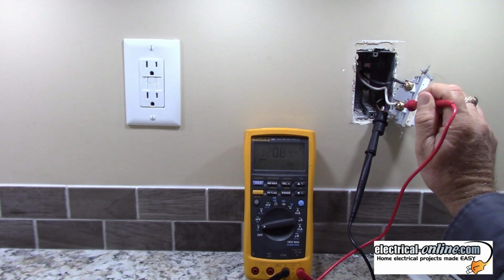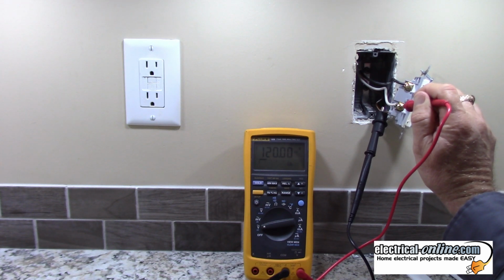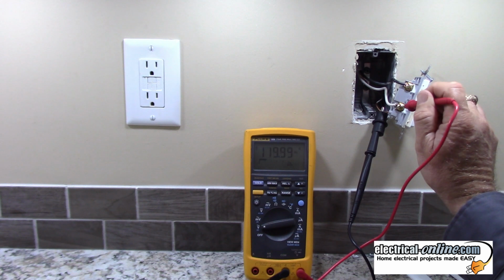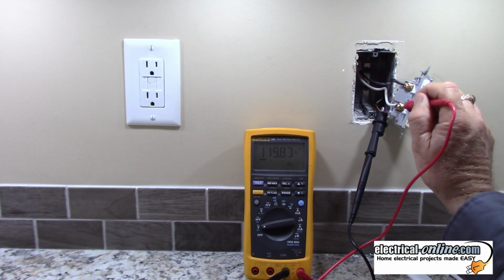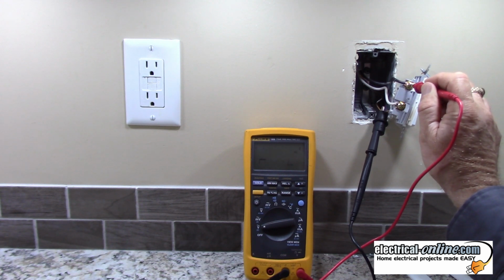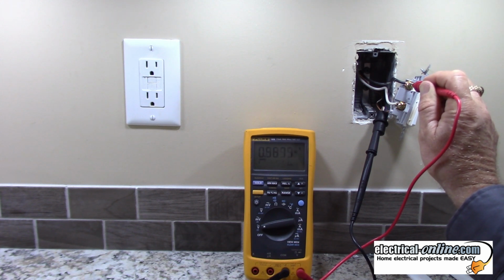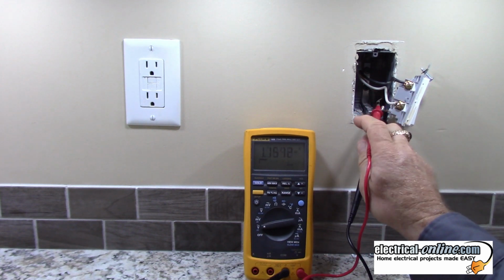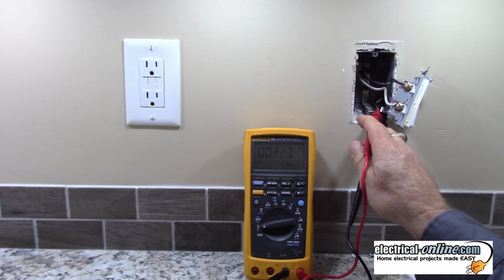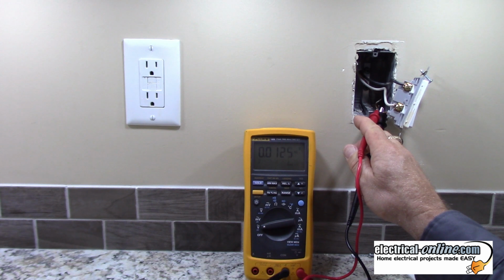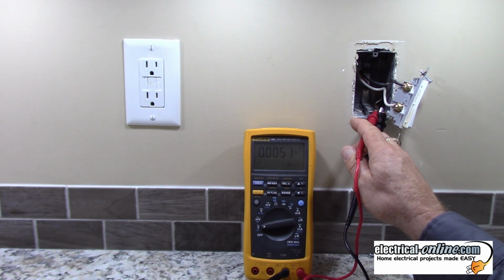And then we should only have power on one terminal, and that's the white, which is being used as a hot in this case. So there you see 120 there now on the white, and close to nothing on the black. We have less than a volt there. That would just be induced voltage. Double check to ground. So both leads are touching ground, and you have 0 volts, 0.000.